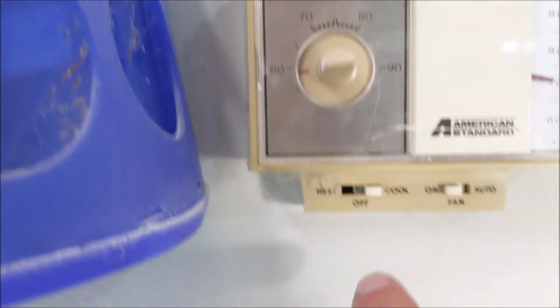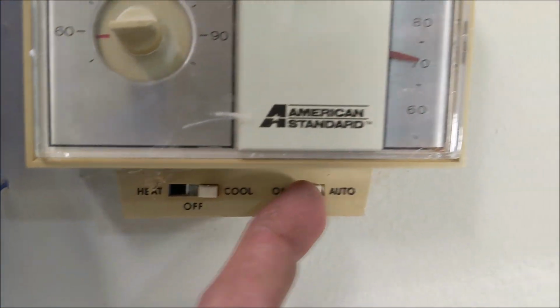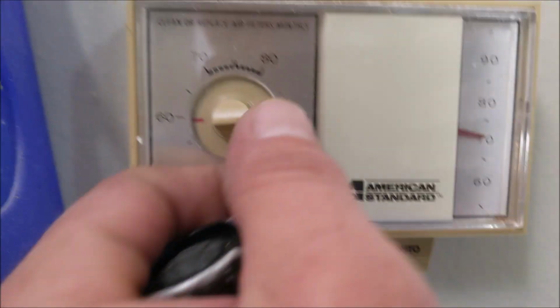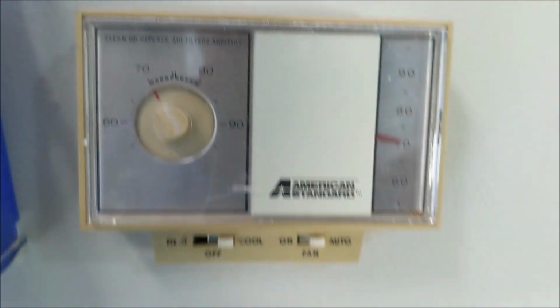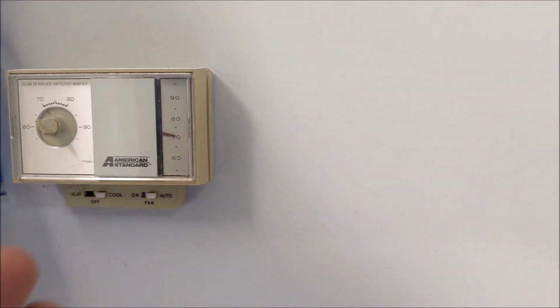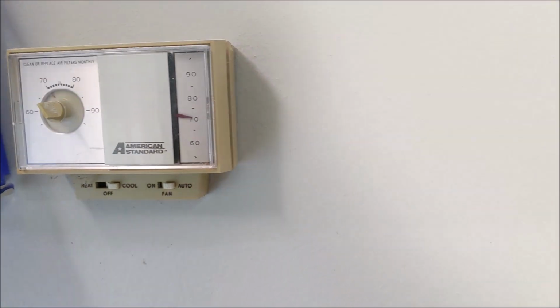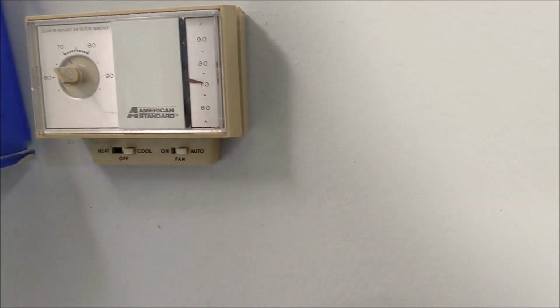So right now I had it set to 60. I had it on cool and it's on auto, so I'm just going to turn it off, turn this back to where the setting was at 70, and let you know we're not going to be able to test the electric heat or the cooling because the fan blower is inoperable. So just have that capacitor checked out.